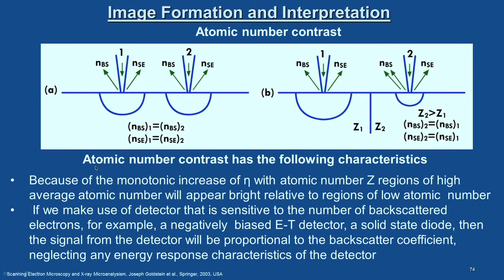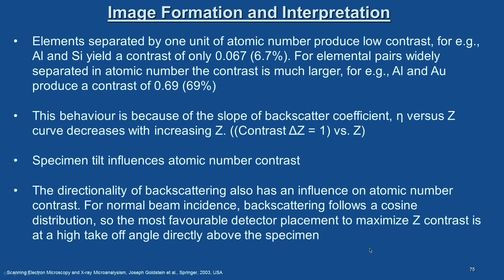Let us look at the general remarks. Atomic number contrast has the following characteristics: because of the monotonic increase of η — the backscatter coefficient — with atomic number Z, regions of high average atomic number will appear bright relative to regions of low atomic number. If we use a detector sensitive to the number of backscattered electrons — for example, a negatively biased ET detector or a solid-state diode — then the signal will be proportional to the backscatter coefficient, neglecting any energy response characteristics of the detector. Elements separated by one unit of atomic number produce low contrast; for example, aluminium and silicon yield a contrast of only 0.067, that is 6.7%.